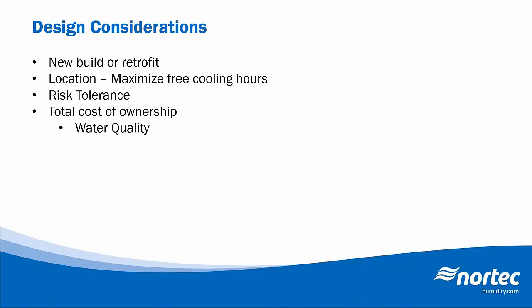So let's take a look at just a few of the key design considerations when you're looking at an adiabatic system. The first is, of course, is this a new build or is it a retrofit application? Certainly the max savings potentials are available if the adiabatic system is included during the initial design phase. Evaporative media systems and atomizing nozzle systems, in most cases, require a ducted air distribution system. As I mentioned, if it's a nozzle system, 4 to 5 feet of unobstructed duct. So if we have to retrofit it, it may not really be a cost-effective solution depending on the conditions or how much cooling we can achieve from that system.